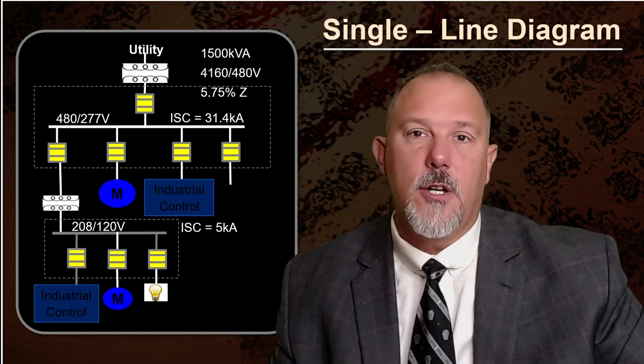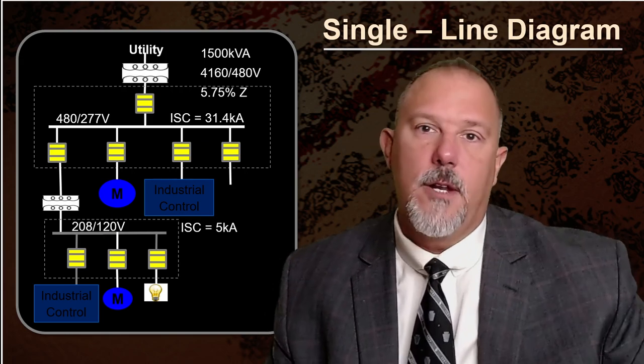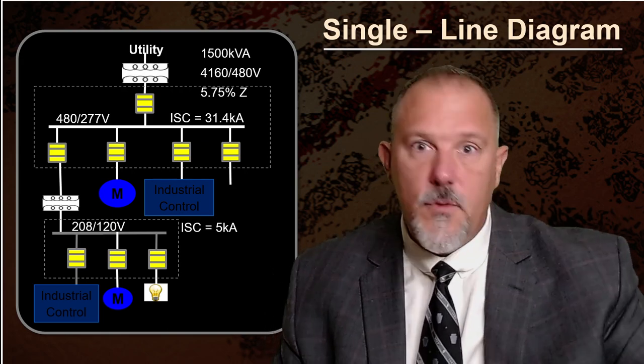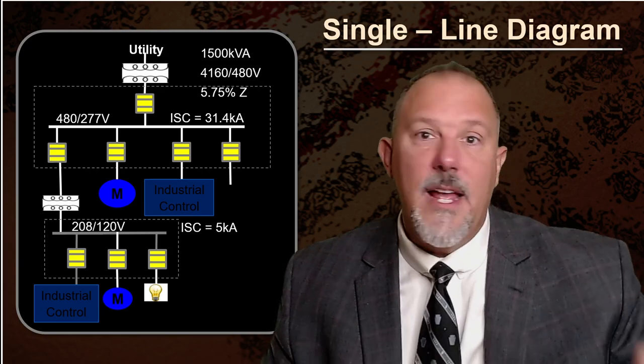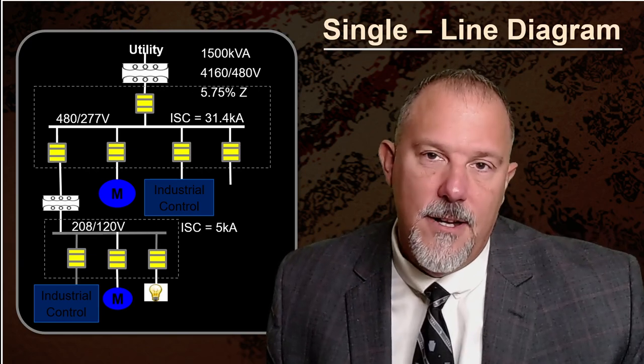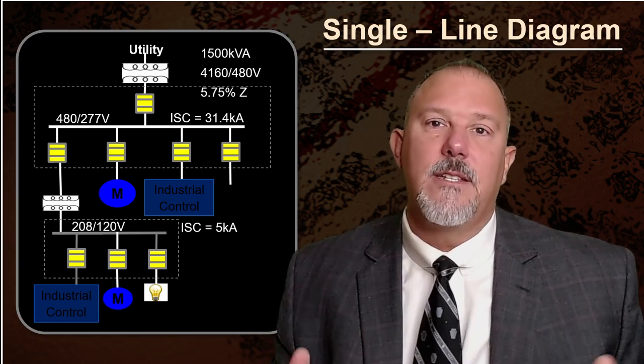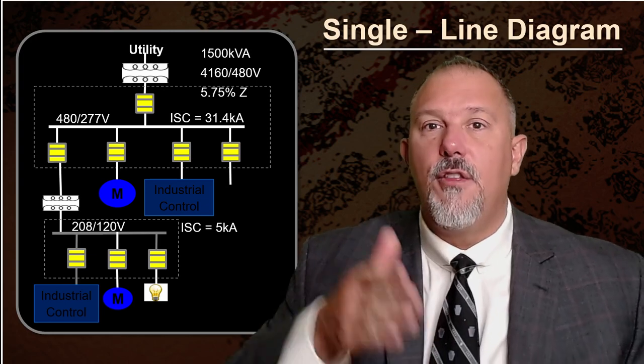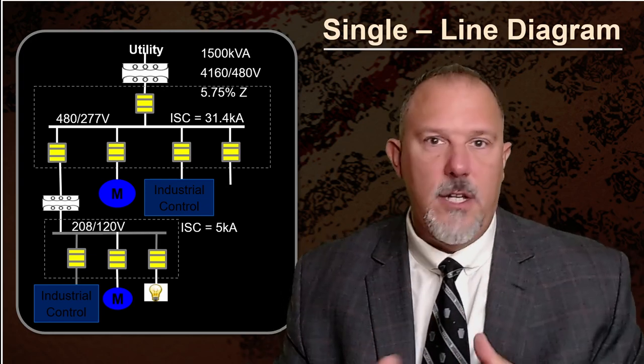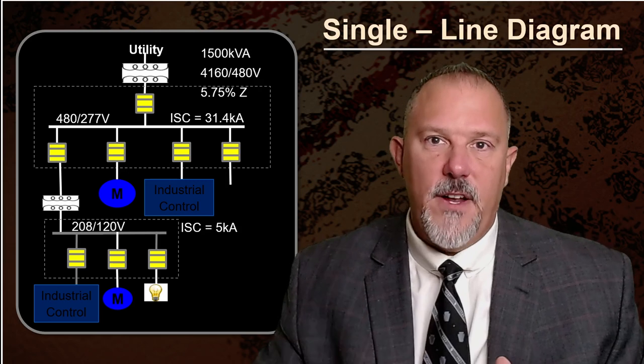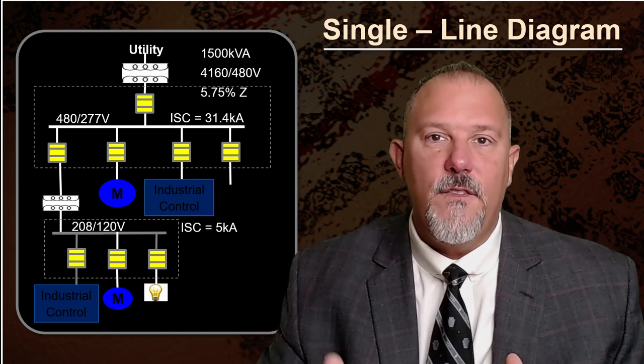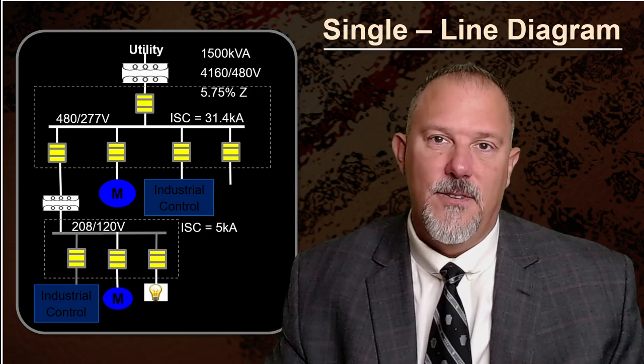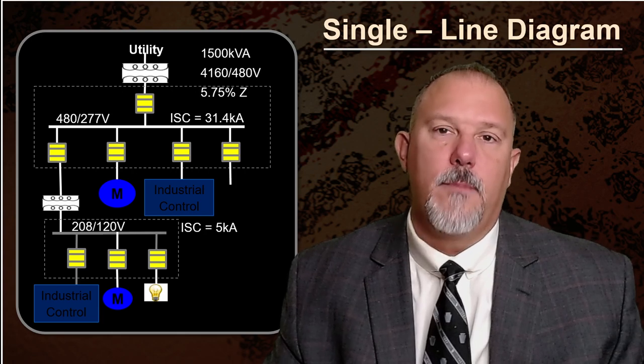Did they put an arc reduction maintenance switch there or an energy reduction maintenance switch? Do they have zone selective interlocking? Do they have arc quenching technologies? Are they able to address the incident energy? Did the design engineer think about that? These are all things you need to think about from a severity and likelihood standpoint. And the qualified person will know exactly what I'm talking about.